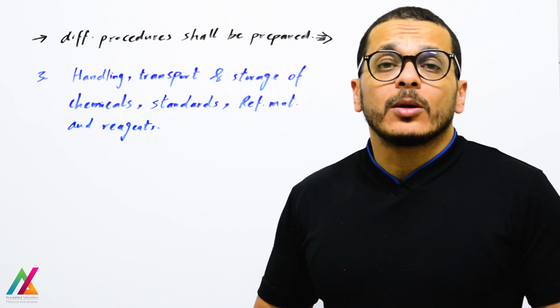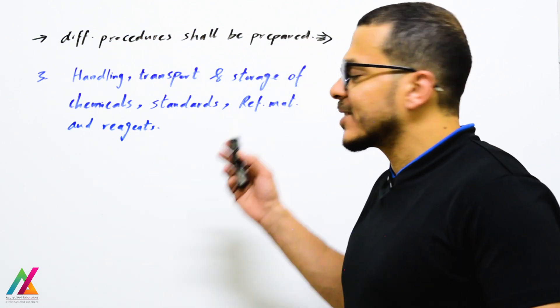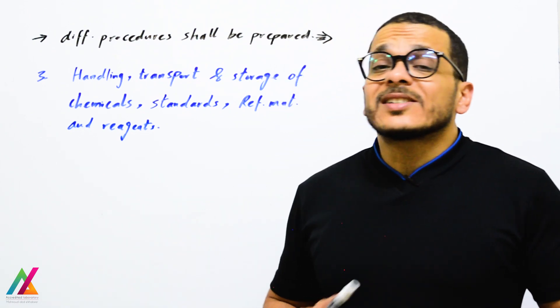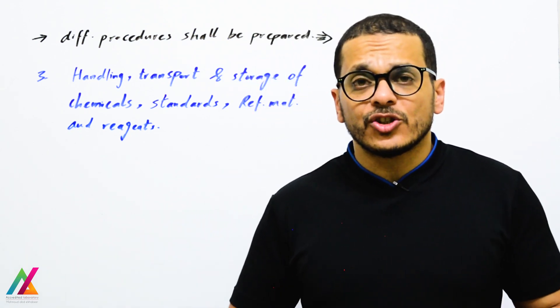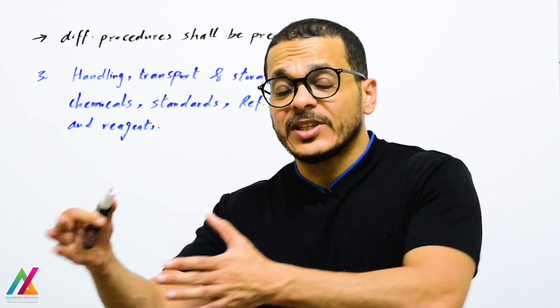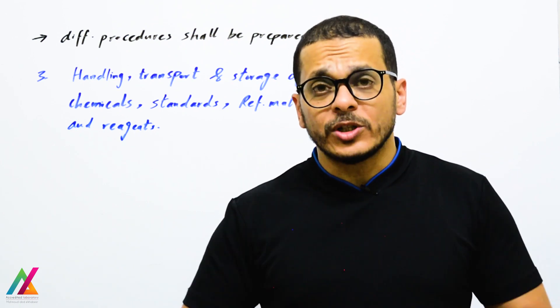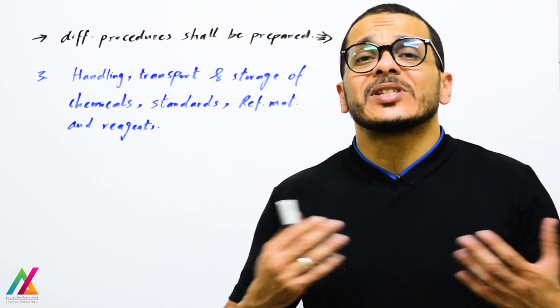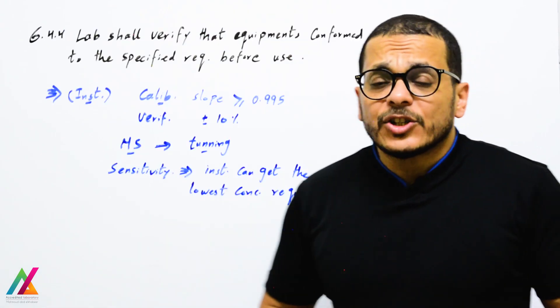A third procedure shall cover handling, transport, and storage of chemicals, reagents, standards, and reference materials — since in the 2017 edition these are all considered equipment. Prepare an SOP for each instrument, a general maintenance procedure (preventive and emergency) as applicable to your lab, and a procedure for handling, transport, and storage of chemicals, reagents, reference materials, and standards. These will vary from lab to lab based on your specific rules.